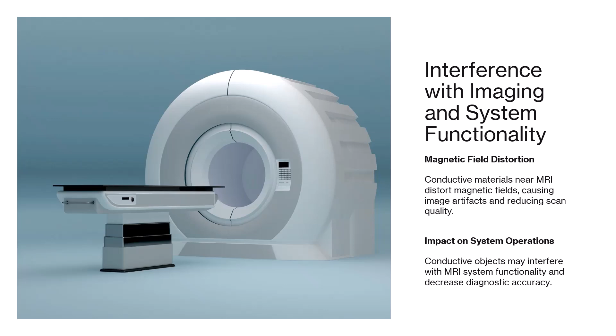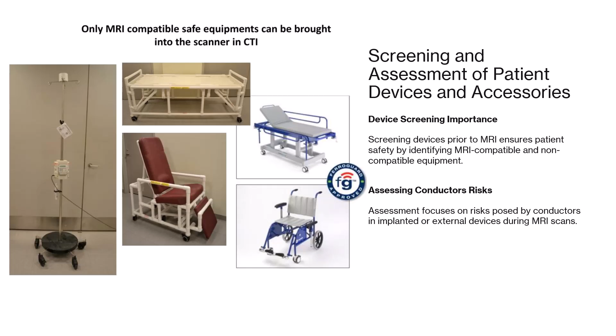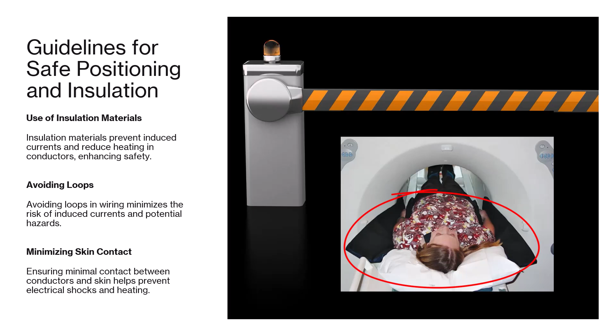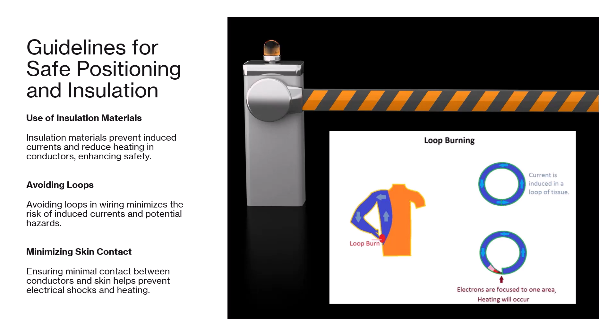Prior to MRI scans, thorough screening of any implanted or external devices such as cables and accessories is necessary to evaluate MRI compatibility and assess risks related to conductors. Proper positioning and use of insulation materials can reduce the chance of induced currents and heating in the conductors. Avoiding loops and ensuring minimal contact with skin are key safety steps.